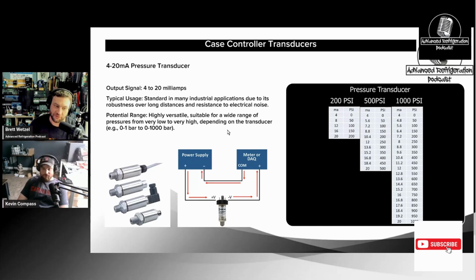Even HVAC controls, anything with controls, it seems like 4 to 20 because it's more accurate if you really think about it. A lot of life safety stuff is 4 to 20 milliamps because there's a safety factor built into it. It's not 0 to 10 or 0 to 5, because if you're looking at a 0 to 10 or 0 to 5 volt signal at 0, you may not know if the sensor's ever bad. Agreed. So that's why 4 to 20 milliamps, you'll see a lot more on life safety stuff, leak detectors, stuff like that.